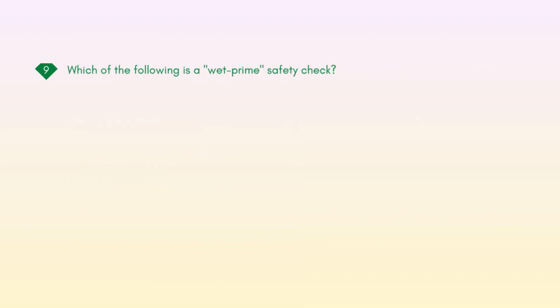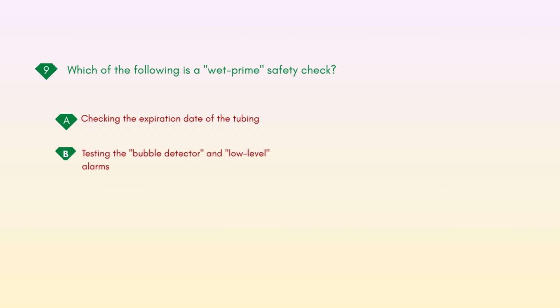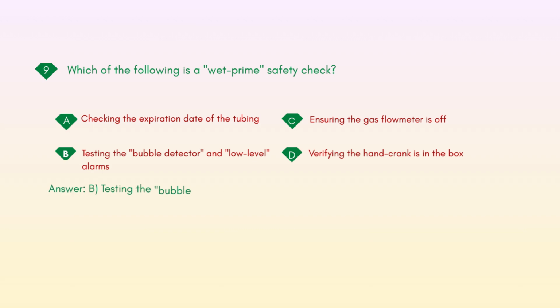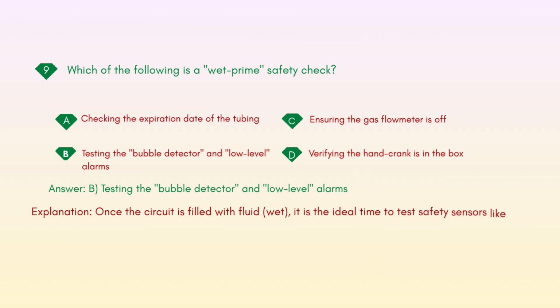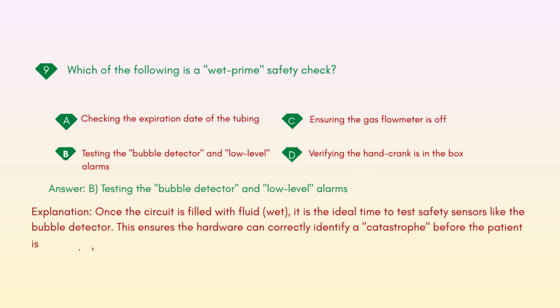Which of the following is a wet prime safety check? A. Checking the expiration date of the tubing. B. Testing the bubble detector and low-level alarms. C. Ensuring the gas flow meter is off. D. Verifying the hand crank is in the box. Answer: B. Explanation: once the circuit is filled with fluid, wet, it is the ideal time to test safety sensors like the bubble detector. This ensures the hardware can correctly identify a catastrophe before the patient is connected.